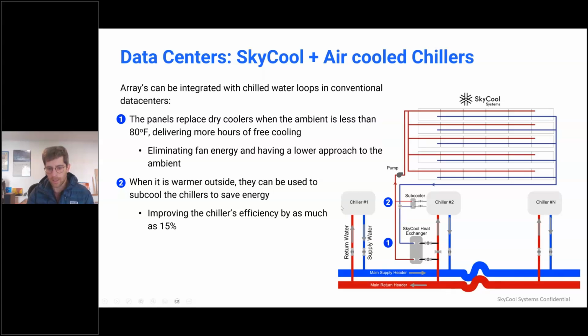And so you can see in this case, this would be a place or a facility that has n chillers. And in this case, we're just modifying chiller number 2. But in cooler times, we're essentially going to add bypass valves into the return chilled water system to this chiller, and cool that water loop with our array when we can, and that can essentially have a much better energy savings in the lower ambient conditions. And then when it's hotter outside, we can subcool the chiller.